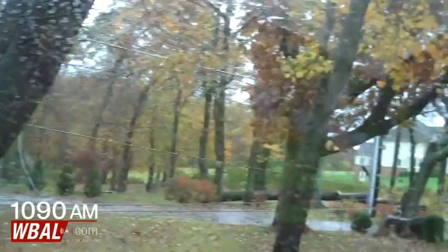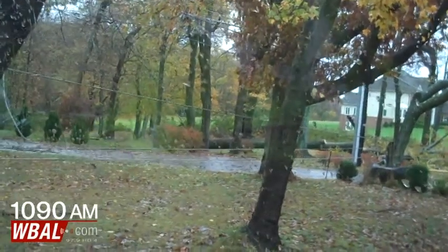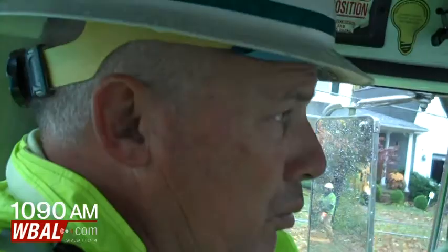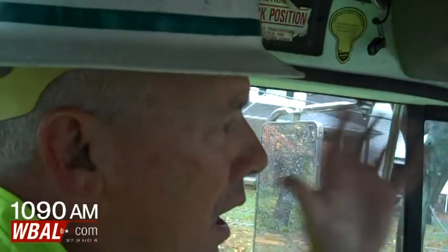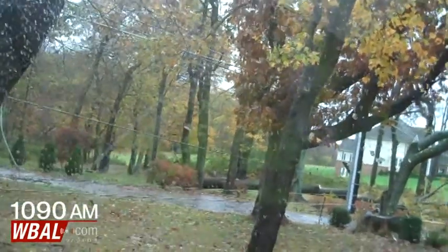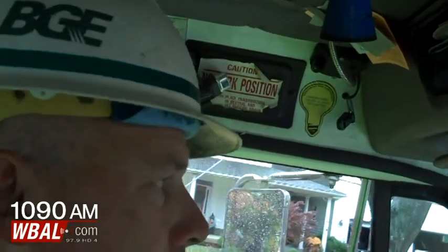This customer's yard — the tree blew over. If you go over and stand at the tree where it came out, the root ball came up a good 50 feet from the lines. But such a tall tree — we could spend hundreds of thousands of dollars trimming this whole line. These 33,000-volt lines are the most important lines we have; they feed our substations. We spend a lot of money and time trimming them, but all it takes is one big monster tree to get blown over and smash everything. So even though the base of the tree was far from the line, when you trim trees you have to go further back — it's not just the ones right next to the line.